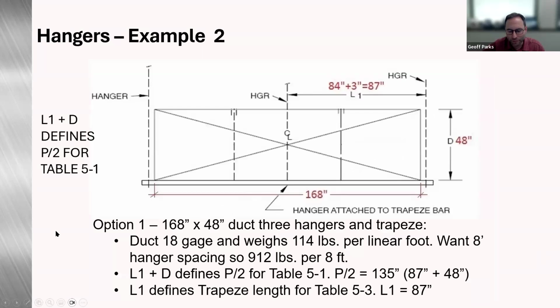So what we have here is option 1. Our duct's going to be 168 by 48. We're adding 3 hangers versus the 2. The duct would be 18 gauge. It would weigh 114 pounds per linear foot, and we're going to have a support or hanger spacing at 8 feet. So that means the duct's going to weigh 912 pounds per 8-foot section.